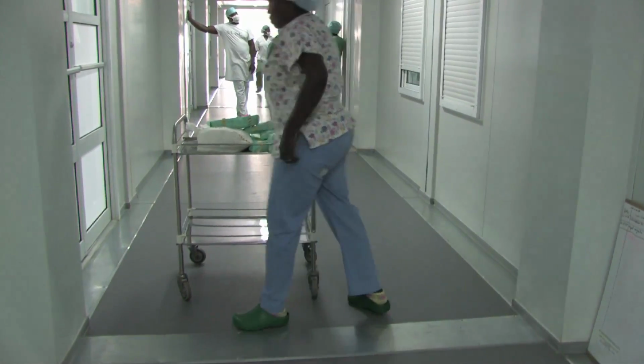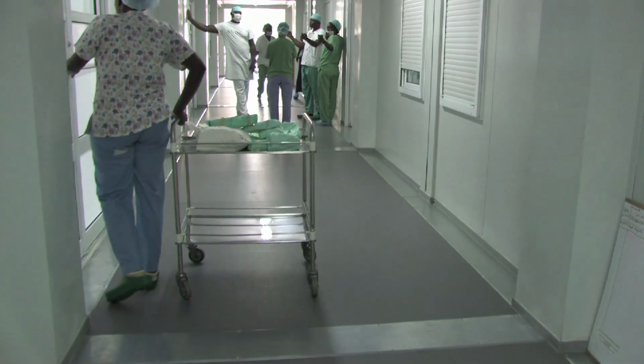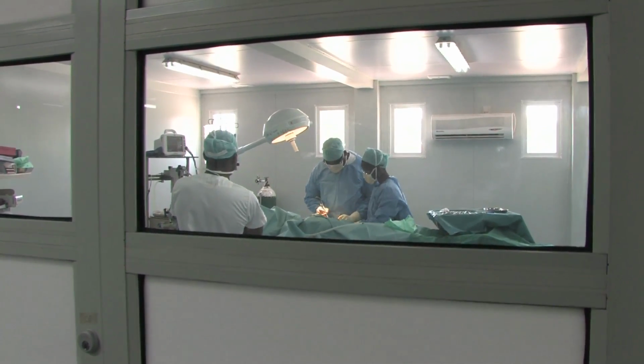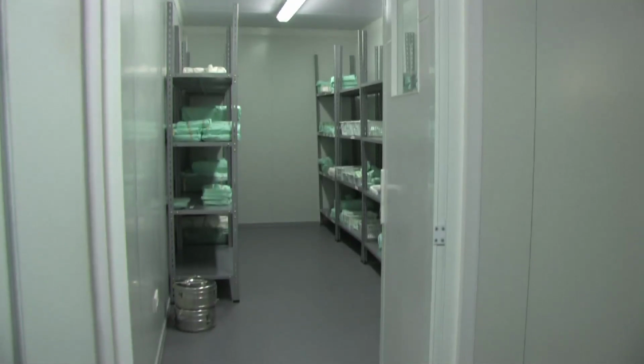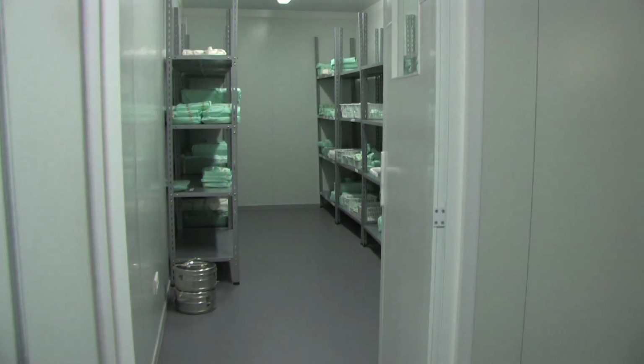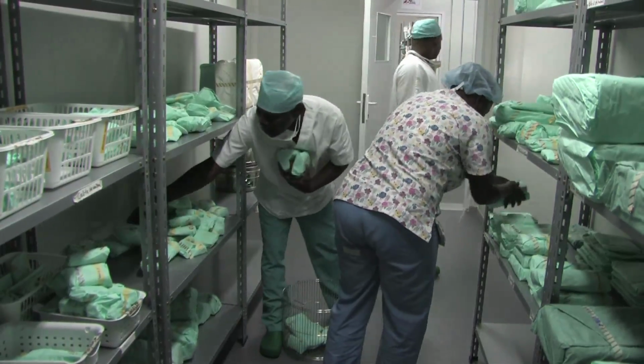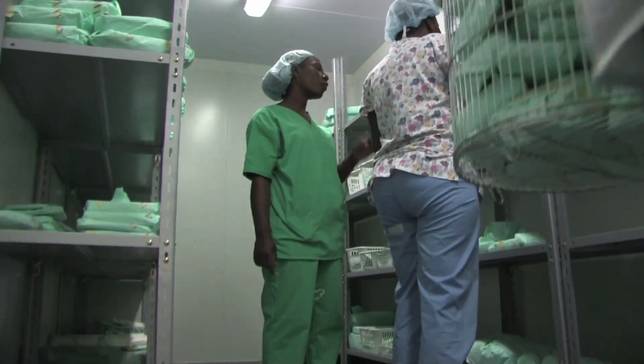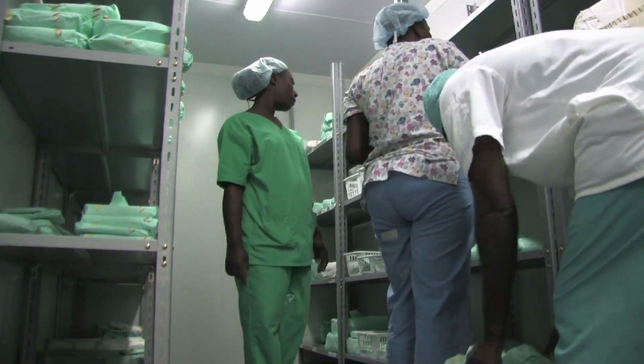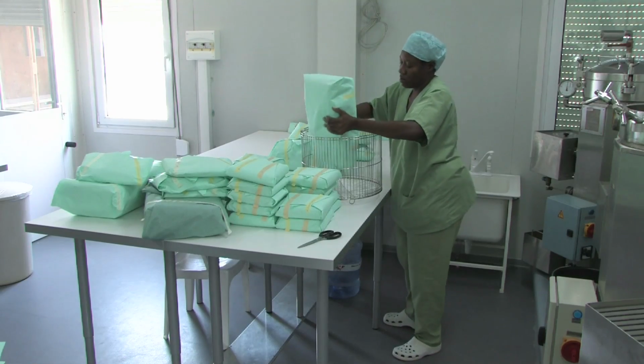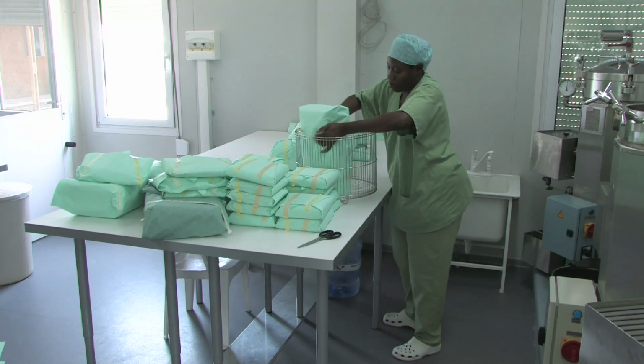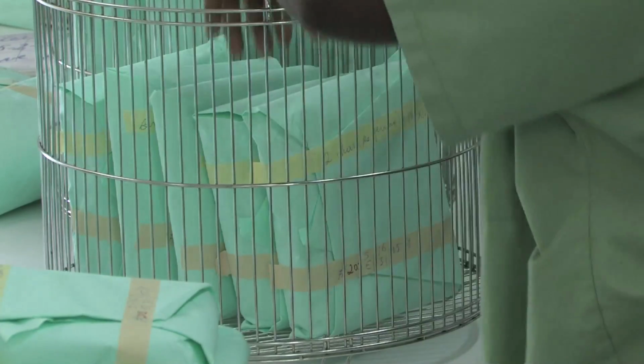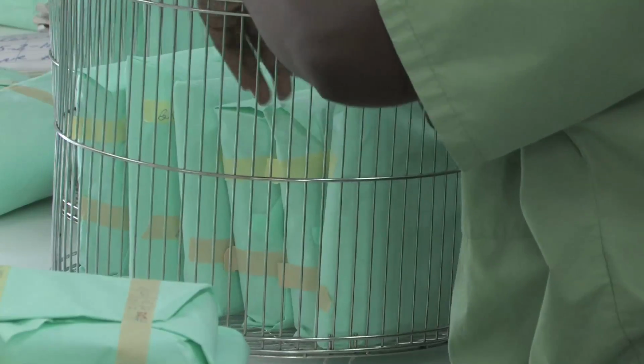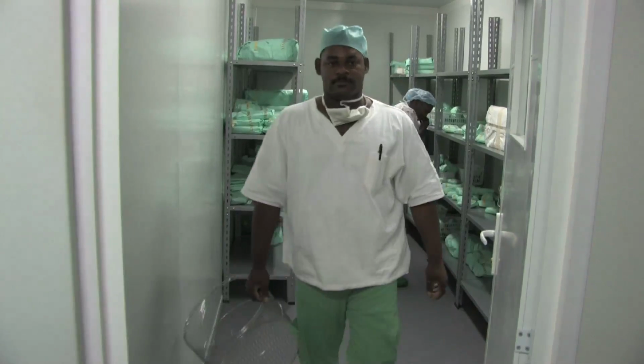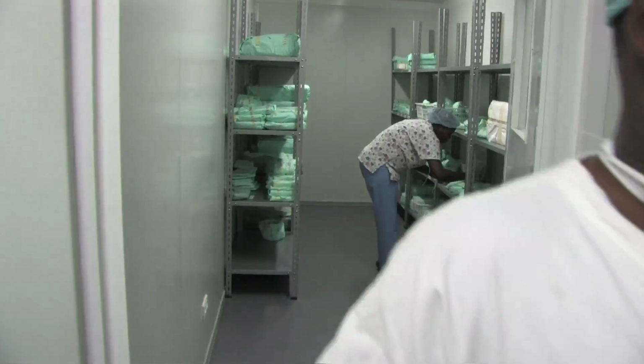After autoclaving, the sterilized packs are transported to their place of use or stored in a clean location away, protected from dust and humidity. They should be handled carefully and protected from potential tearing. The packs should be put away according to their expiration date. Given the working conditions in the field, lack of instrument washers, water treatment, air treatment, and sophisticated autoclaves, sterilized packs should not be stored longer than 2 weeks.